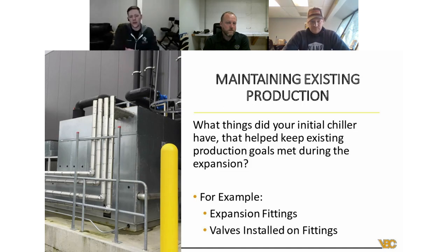So keep in mind what your facility has potential for growth, and know what's available to you to grow with the current chiller. We were in a situation when we brought in our new chiller where we didn't have a place to tie in the existing system when running new piping. So we had to build new fittings, shut down the system for a couple hours, install them, and then reconnect the old chiller to the new fitting.